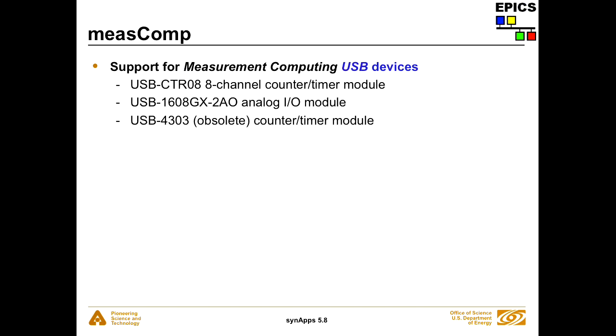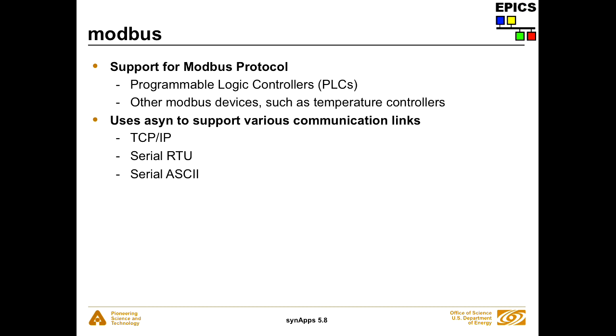The measComp module supports specific Measurement Computing devices, and I think they're all USB devices. Modbus was originally to talk to Modbus PLCs, but it can also talk to other Modbus devices — a lot of panel-mount meters and temperature controllers speak Modbus. It supports all three main flavors of Modbus: TCP/IP, serial RTU, and serial ASCII.